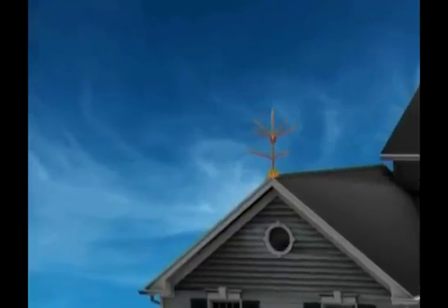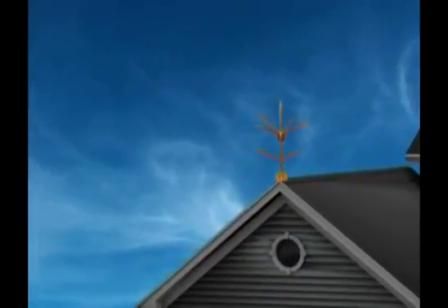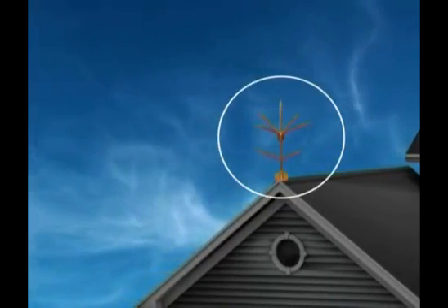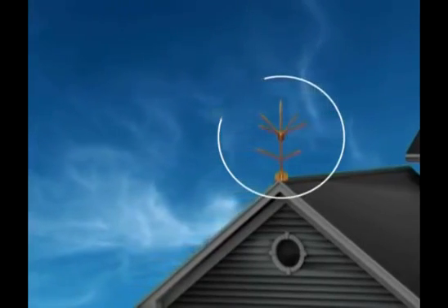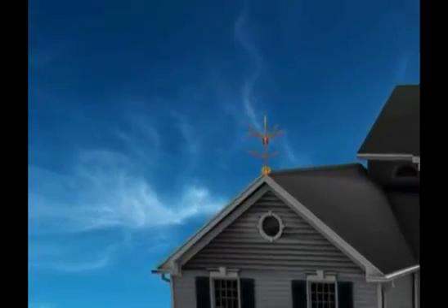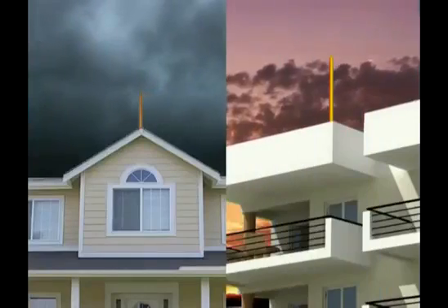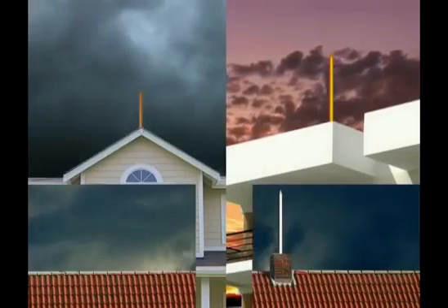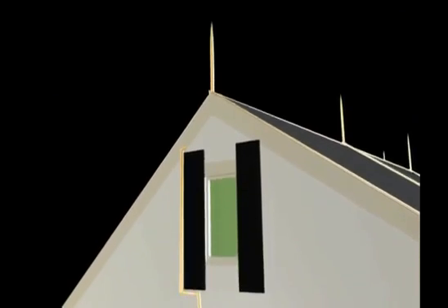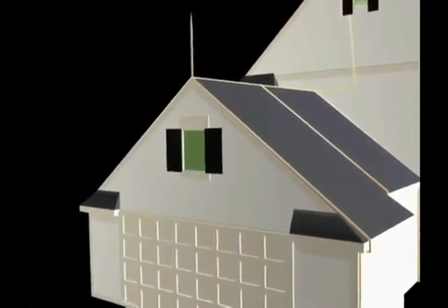There is something else too that needs to be remembered. The varying shapes seen at the tips of air terminals do not offer any special protection. The air terminal does not need any complex shapes. In buildings with heights of 60 meters or more, the risk of a strike is not confined to the top alone. Since the sides of the building too are vulnerable to attack, the edges of the buildings too are to be secured to the air terminals and down conductors.